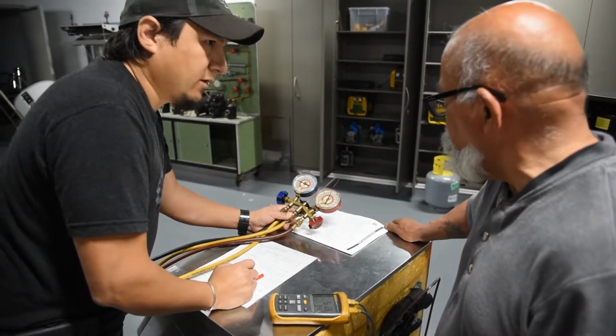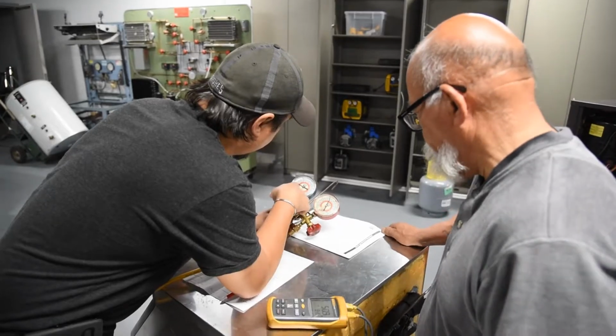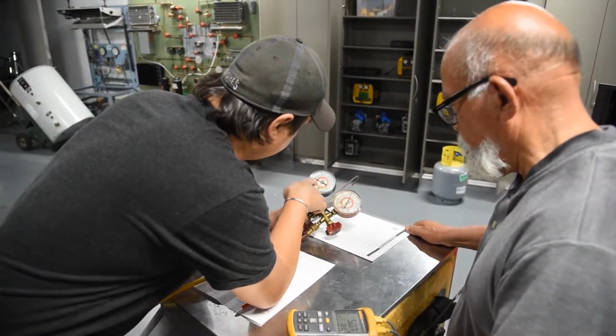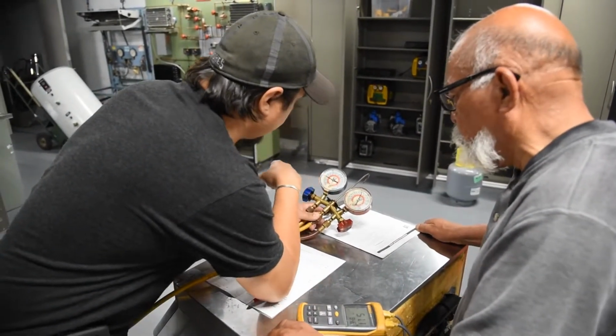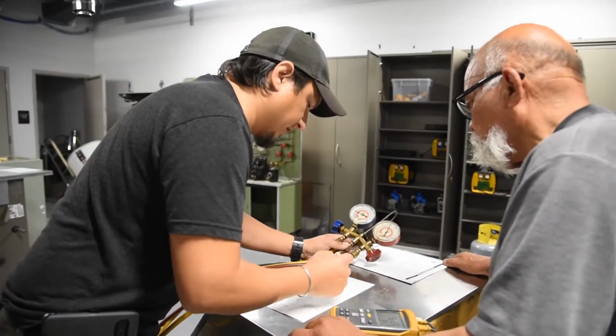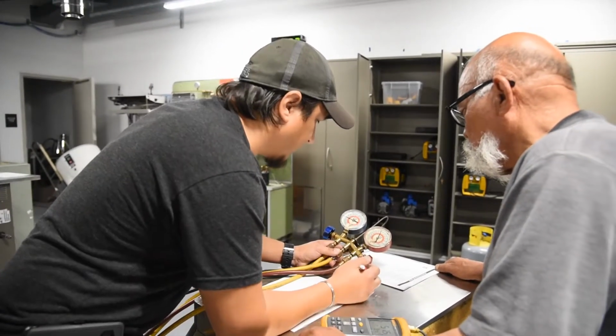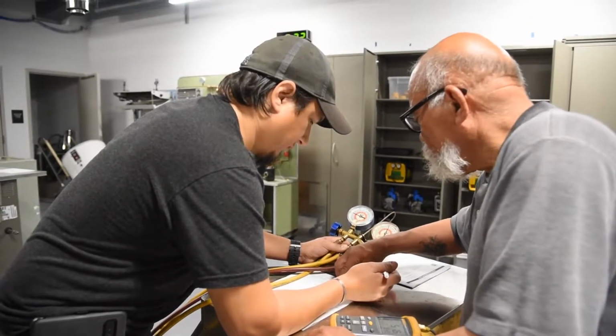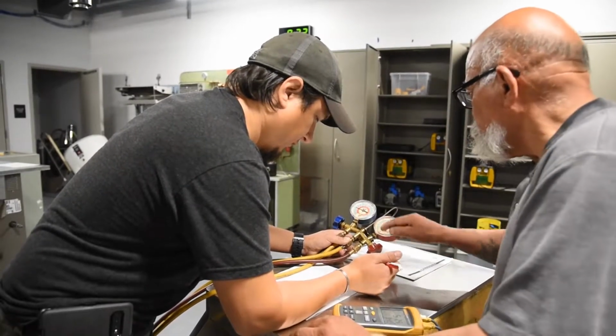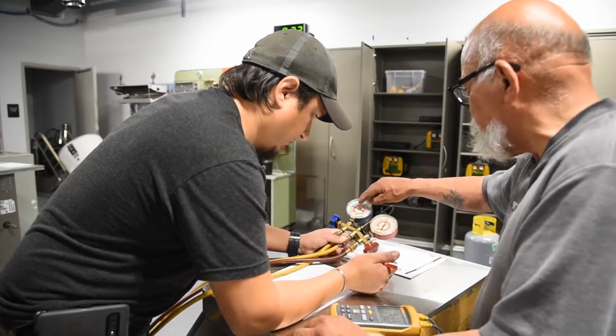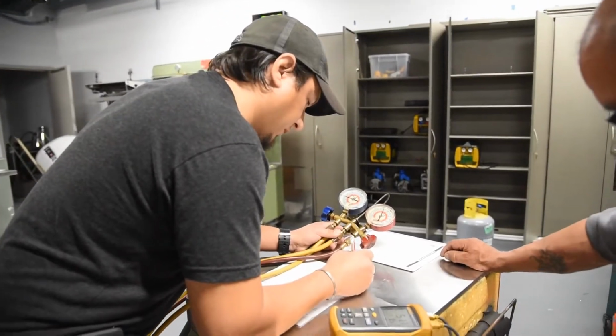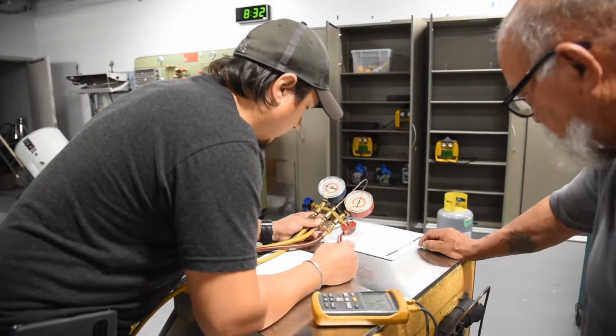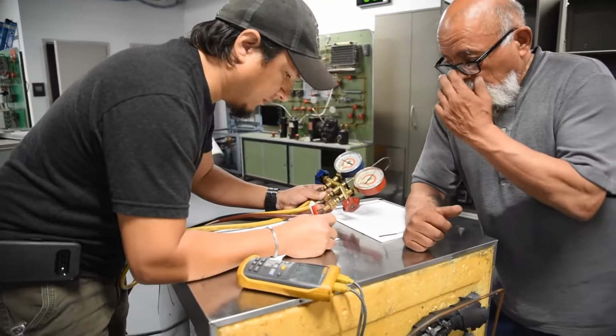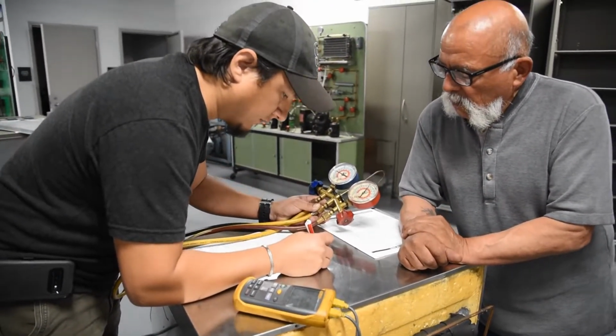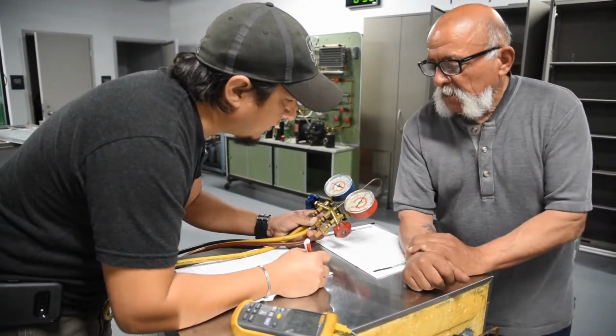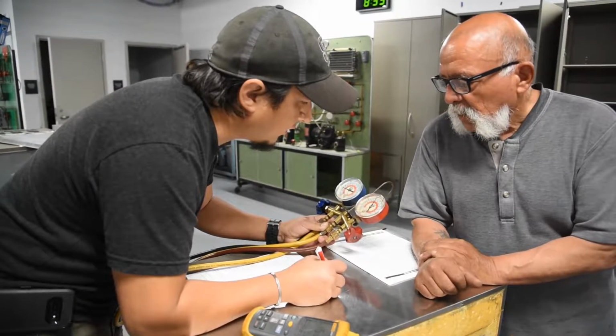Correct. How about the low side? What's the pressure temperature on the low side? The low side is 50 PSI, and then our PT chart indicates that for 404A is 15 degrees. Okay, so what was it 5 minutes ago? Oh, 5 minutes ago, on the low side, it was 65 PSI and 25 degrees temperature. Okay, go ahead and put the low side. We'll mark that 1, 2, and 3. We'll put another mark, another data point there, what it's doing partially through the process. Okay. So right now, low side, 50 PSI. High side we're 310. And the temperature is 110.